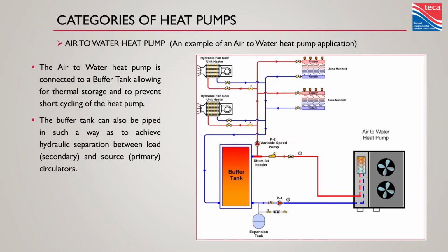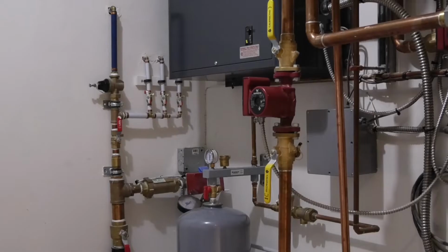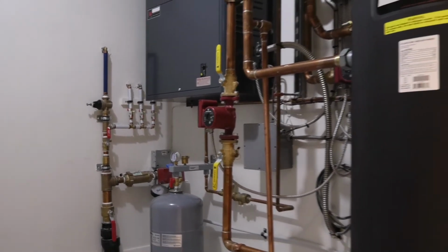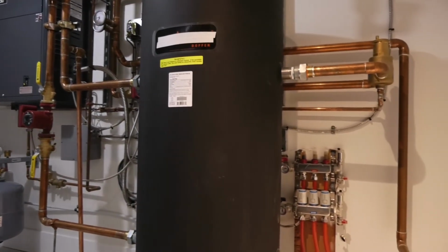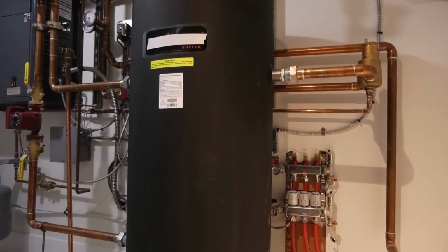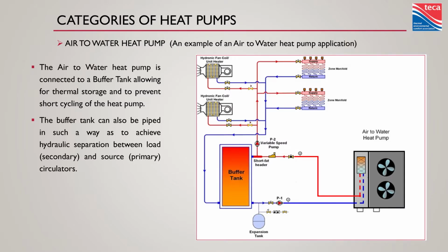I don't know how much you guys know about compressors. They do not like short cycling. Gas appliances don't like it. Electric appliances don't like it. Compressors hate it. So if we can keep them running long, we keep those compressors properly lubricated with oil, we keep the locked rotor amperage draws to a minimum, thermal stress to the wiring to a minimum, and we get a nice efficient system. Buffer tanks are going to be key to that, but buffer tanks create more challenges if we're not used to working with them. I've used them in non-heat pump applications plenty of times, but they are a way of storing energy, and you also have to understand what it's doing to your system.